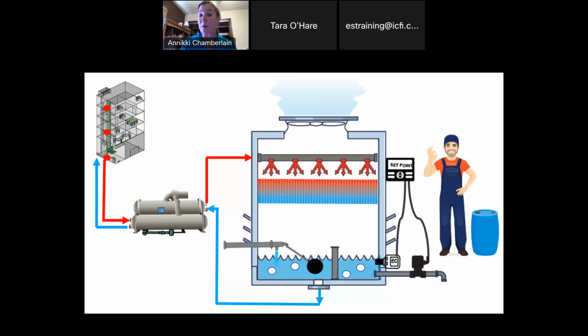What's going on? My coworker was able to see that when they had installed it, they had installed the sensors incorrectly, and it just wasn't in the flow of water. So basically, the towers were scaling up constantly and having to be replaced. So that was basically a failure in how they set it up. But yeah, those sensors, they need to be cleaned regularly.